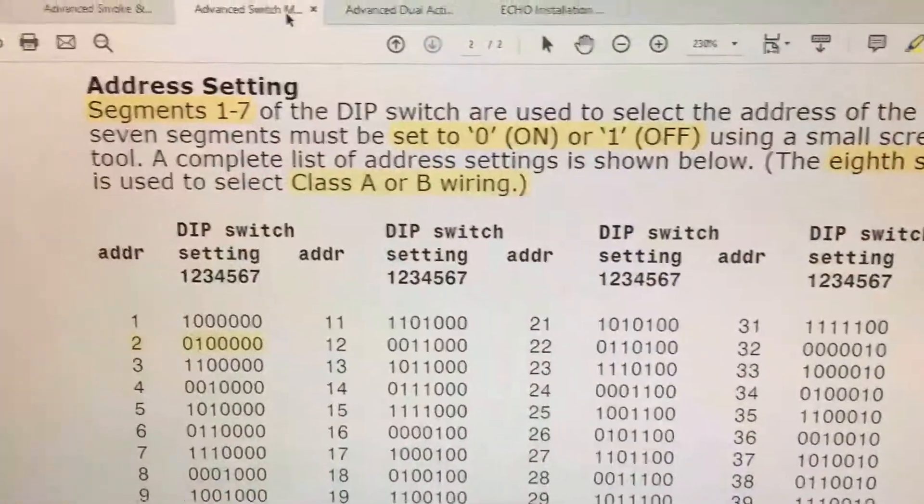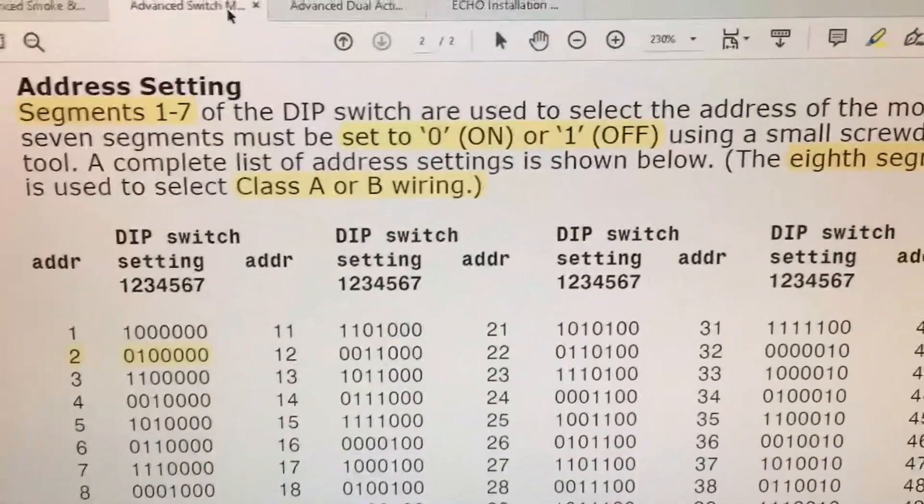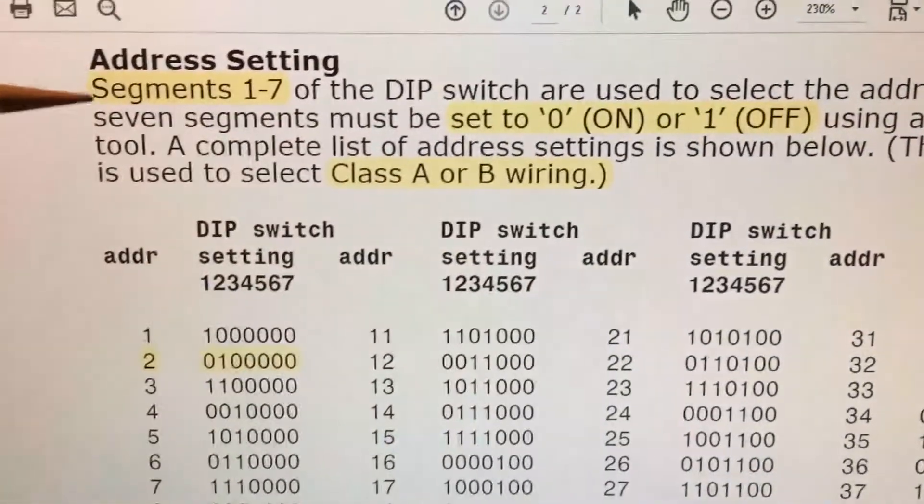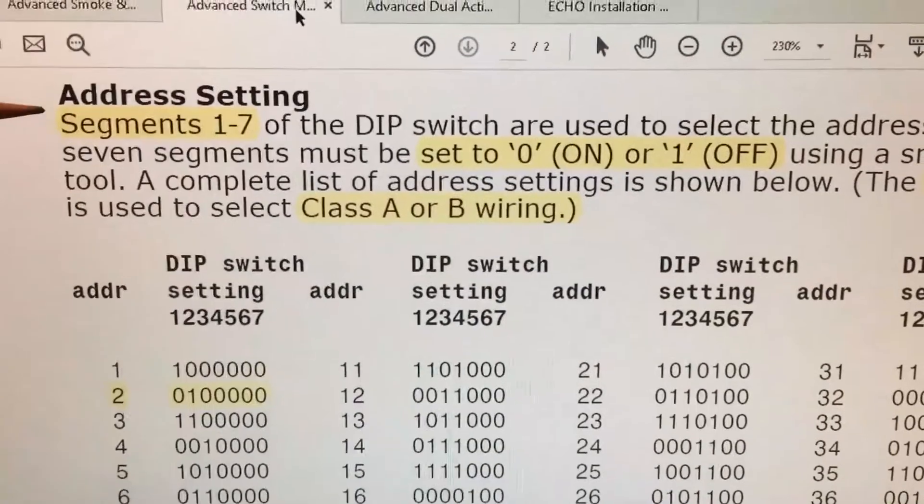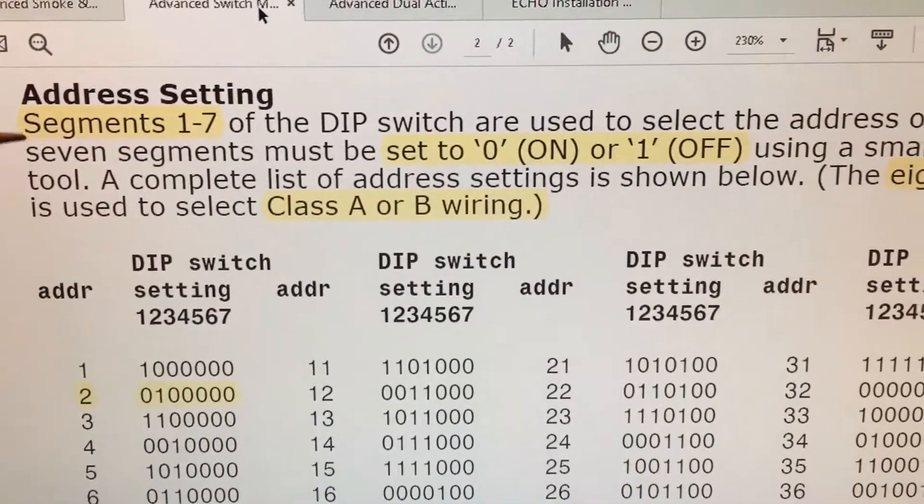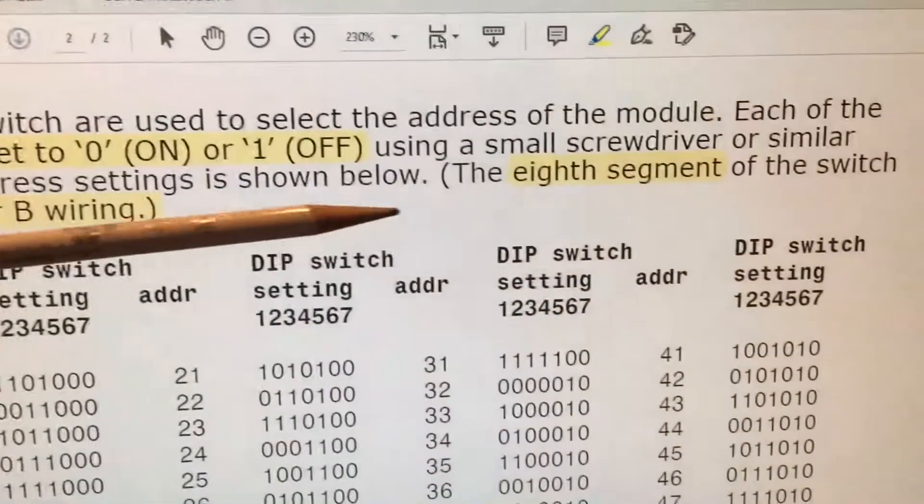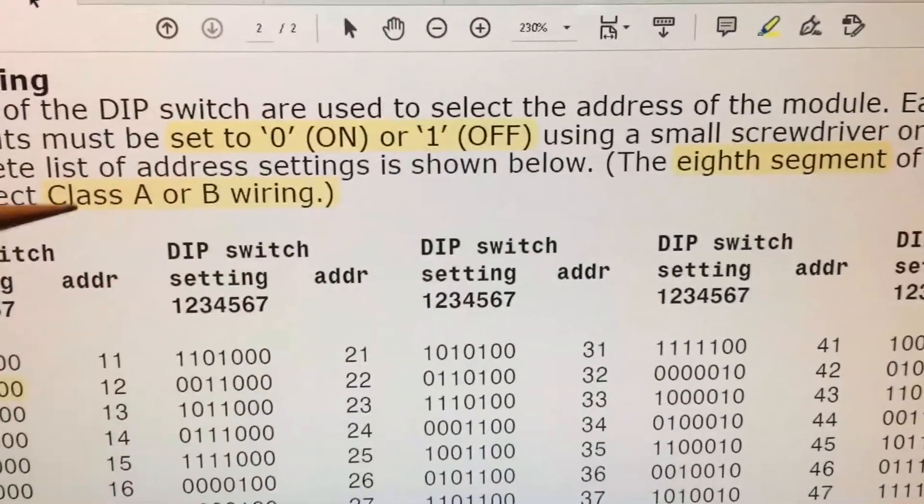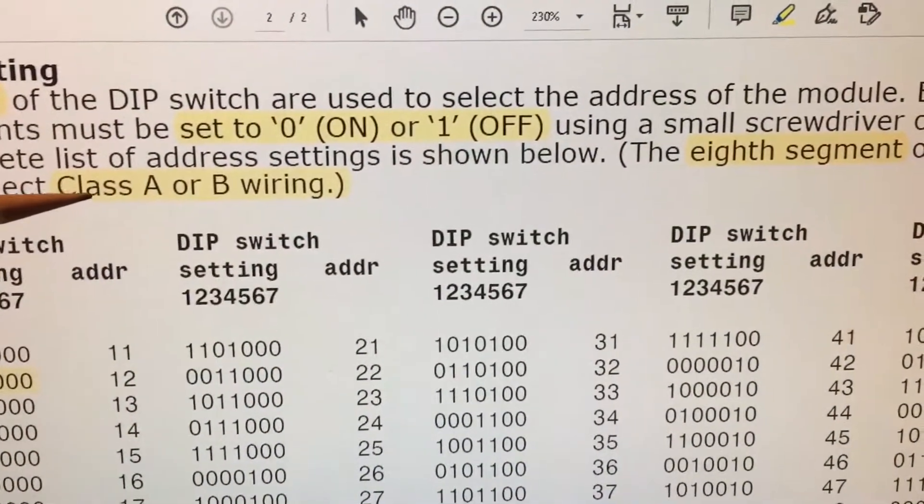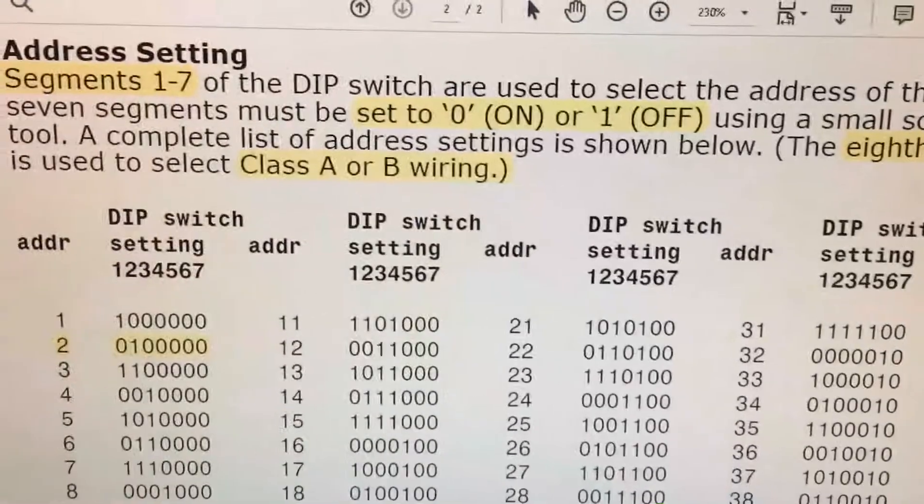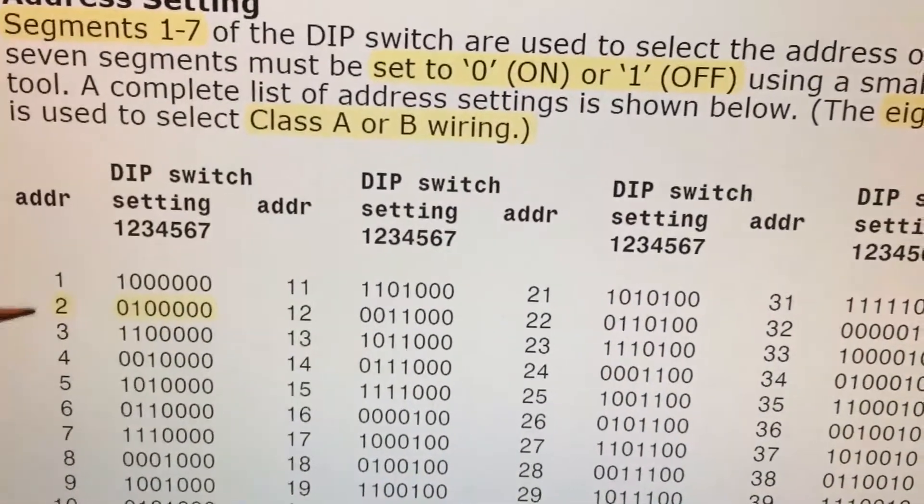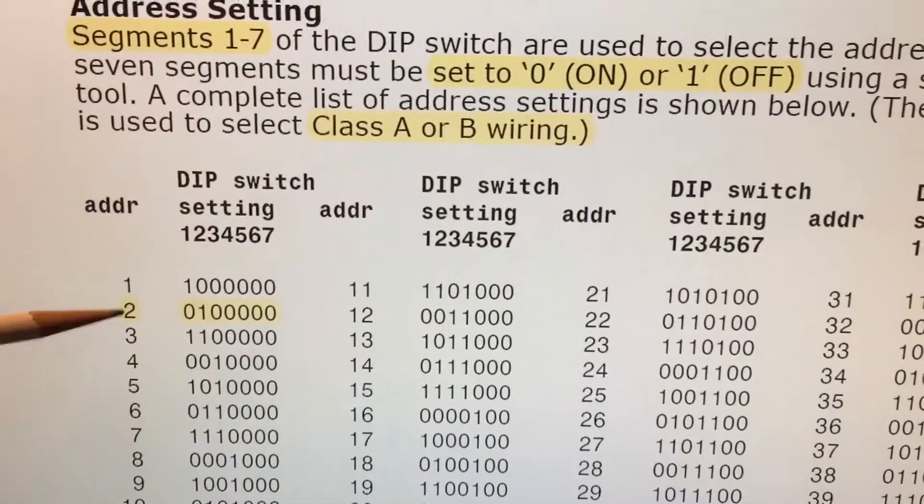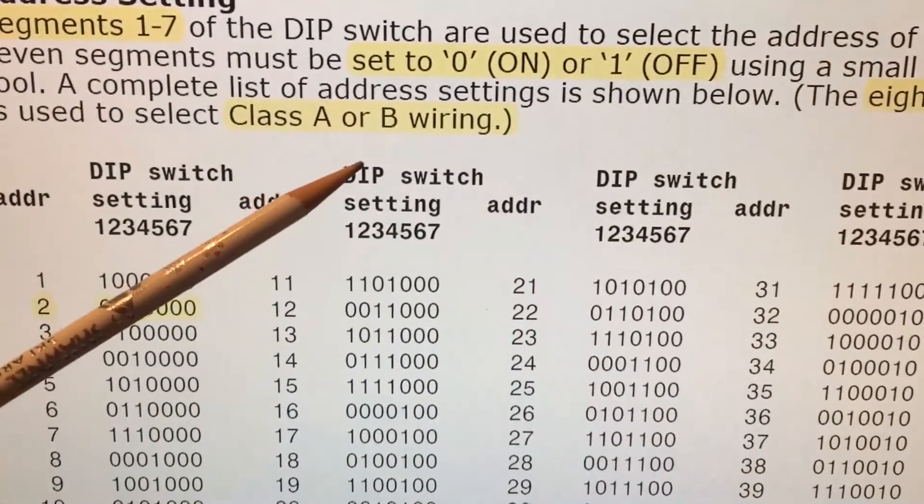Our next device is a monitor module. This one happens to be a single monitor module. Segments one through seven will set the address, whereas segment number eight is what is used to determine whether it's going to be wired class A or class B. In our particular item, it'll be address number two and we will choose class B wiring.